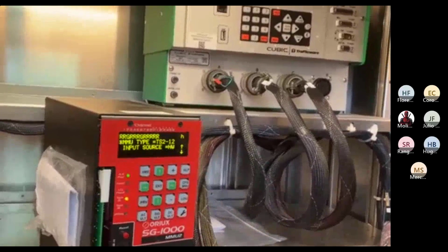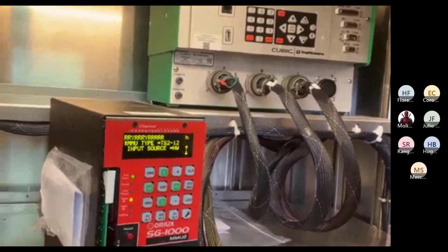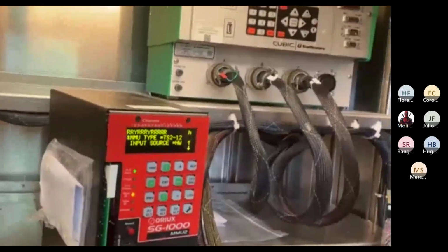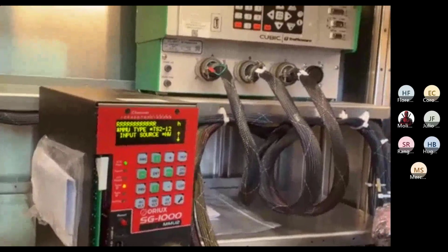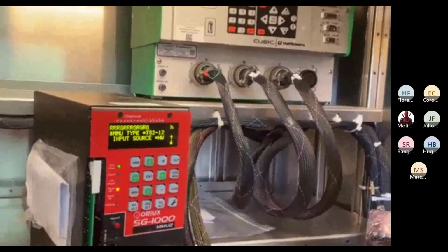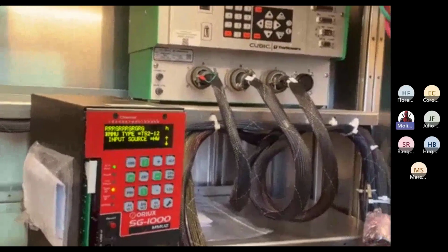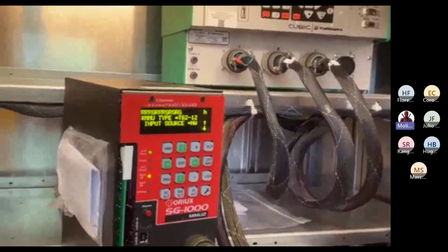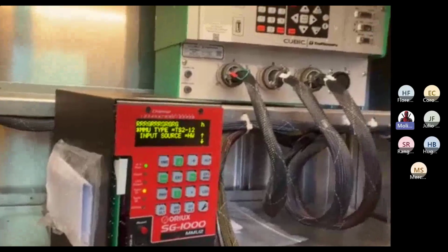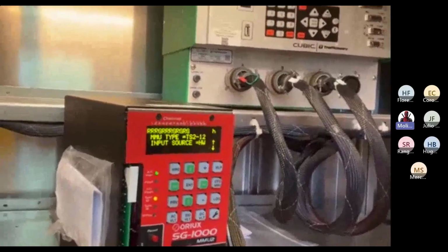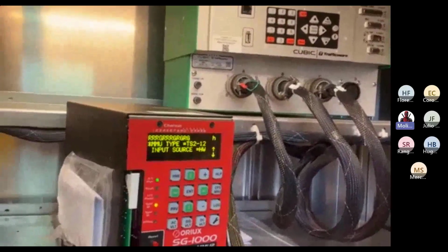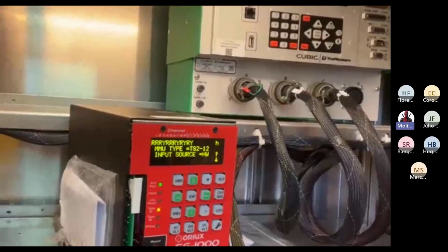Right, with the BIU, because the type select is separated from the SDLC, it's two different settings, right? So the type 12 and type 16 is dependent entirely upon the back panel. Only on the back panel. It's how it's wired. Is it a TS2 back panel? Does it have the type select to make it a type 16? The other stuff, see, you're operating like a TS1.